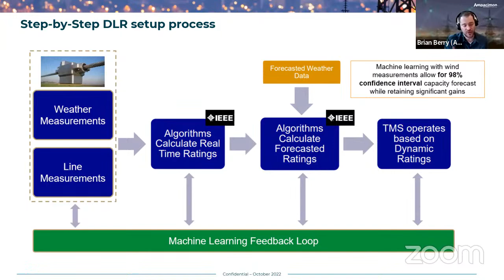With dynamic line rating, yes, it's useful to know what's happening right now, whether I can push extra megawatts through the line. But it's more important to know what's going to happen in a few hours, because when I need to get megawatts onto the line or into the power system, I normally have to arrange that ahead of time. Even better if I can predict what's going to happen tomorrow, so I can start speaking to the power stations today to make sure they come online.